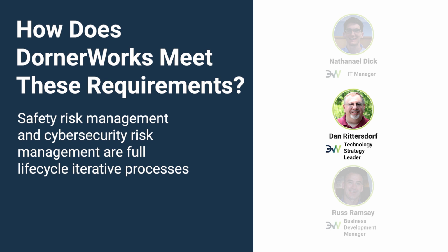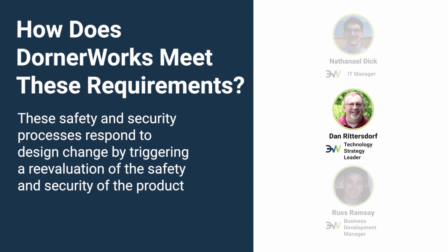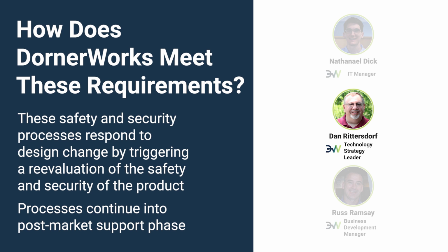Safety risk management is a full life cycle activity, not a one and done prospect. Likewise, our cybersecurity risk management process is being updated to parallel that safety risk management process, with security risk management as a full life cycle iterative process. The safety and security processes are designed to expect design change. Change is the only real constant, and they respond to design changes by triggering a reevaluation of the safety and security of the product. This continues into the post-market phase with our customers as the software bill of materials is monitored for new vulnerabilities, which may trigger a security event, reevaluation of the risk for the medical device, and may result in us developing a patch to resolve the vulnerability. For serious cases, it may involve a recall.